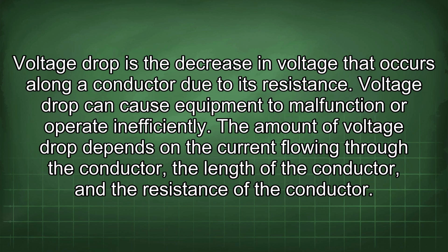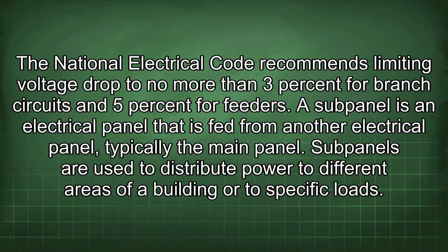Voltage drop is the decrease in voltage that occurs along a conductor due to its resistance. Voltage drop can cause equipment to malfunction or operate inefficiently. The amount of voltage drop depends on the current flowing through the conductor, the length of the conductor, and the resistance of the conductor. The National Electrical Code recommends limiting voltage drop to no more than 3% for branch circuits and 5% for feeders.